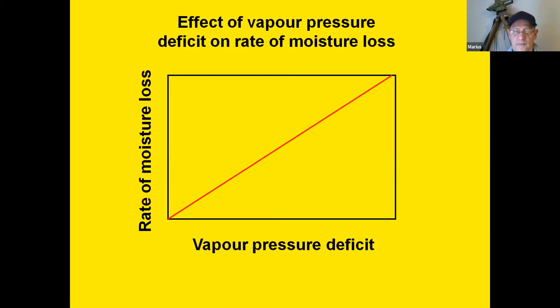rate of moisture loss. Okay, now all of this can be related back to psychrometrics because we need a picture to see how this thing works and to be able to manage it and to predict certain circumstances. So a psychrometric chart, a simple format of which is shown here, basically looks at 5 factors related to moisture in air. It's the wet bulb temperature, dry bulb temperature, relative humidity, specific humidity, and then the water vapor pressure on the right-hand axis. If you have any 2 of these factors quantified, you can deduce from this chart any of the other 3 that you don't know.